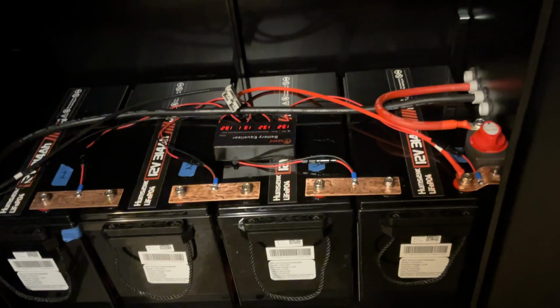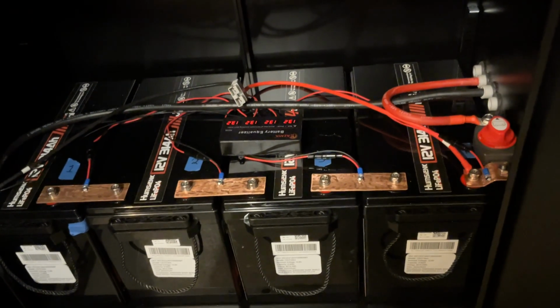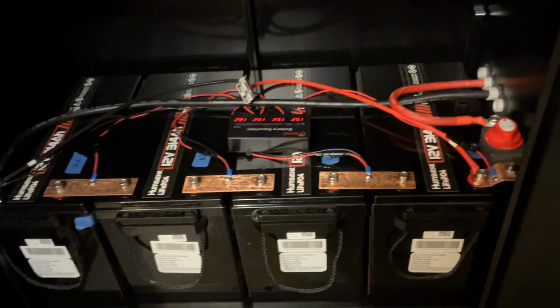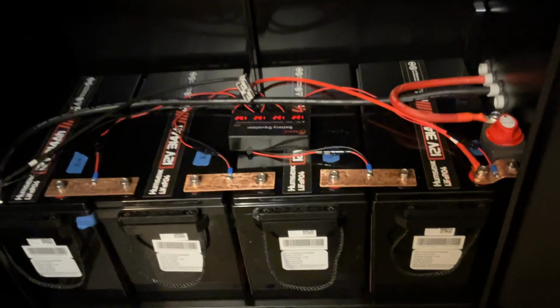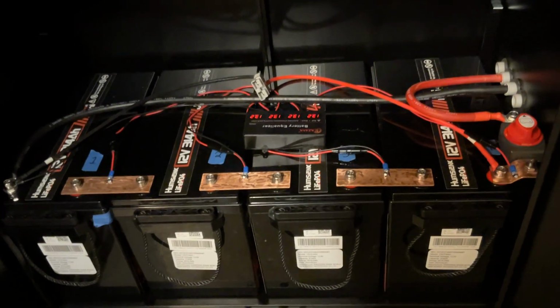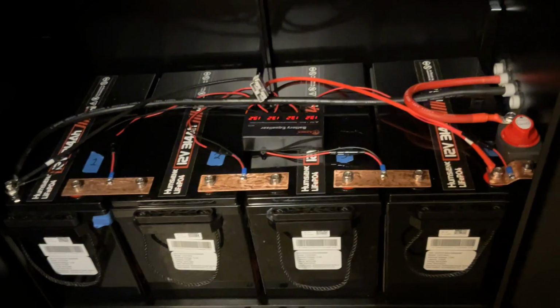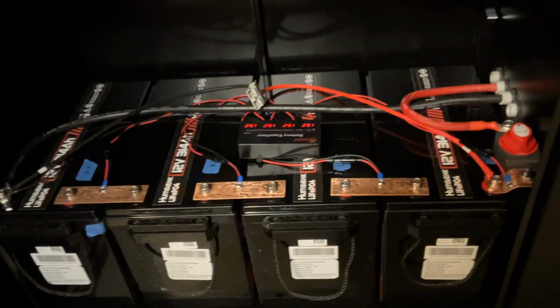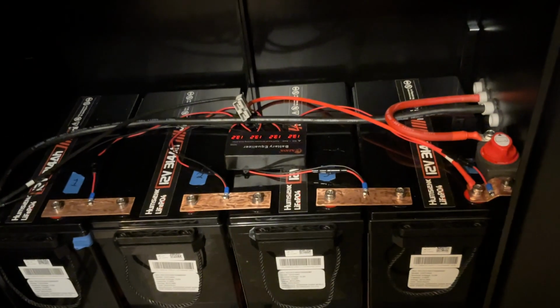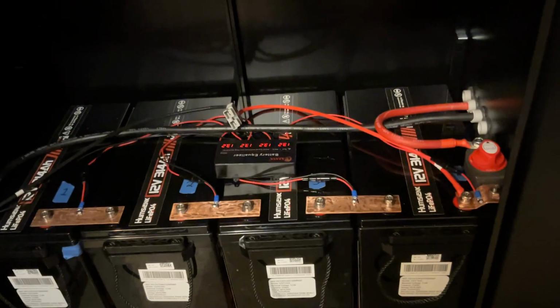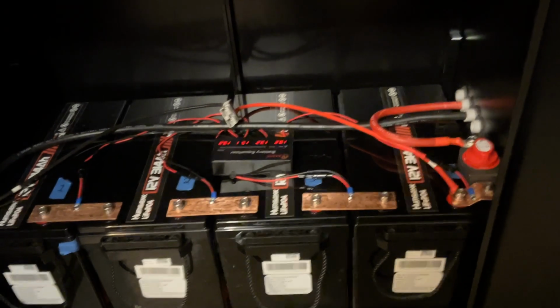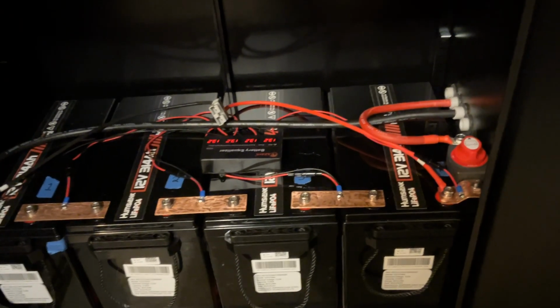The balancer was still feeding power through the wires connected to battery 4, and that's why my inverter still turned on. Once I disconnect that battery balancer and turn off the output FETs for one of my batteries, the inverter won't turn on—there's no power there because that one battery's turned off. So these battery balancers will provide enough current to turn on your inverter even if one of those batteries is turned off.